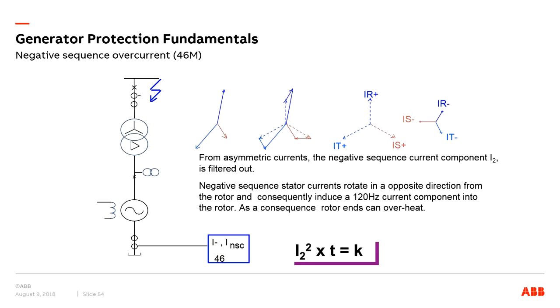The negative sequence impedance of an induction or synchronous machine is approximately equal to the locked rotor impedance, which is approximately 1/6 of the normal machine impedance. Okay, so with a negative sequence current, the rotor gets heated up and there could be severe damage to the machine. So we need to provide adequate protection against negative sequence current, because the heating of the machine is proportional to the square of the current, right? So that becomes more critical.